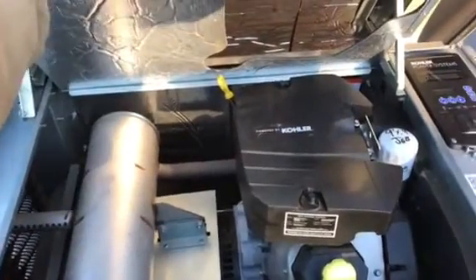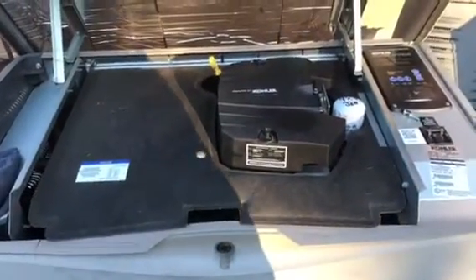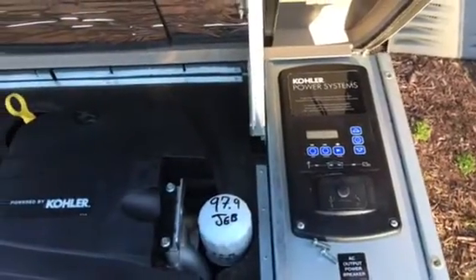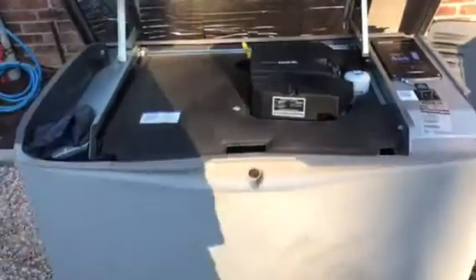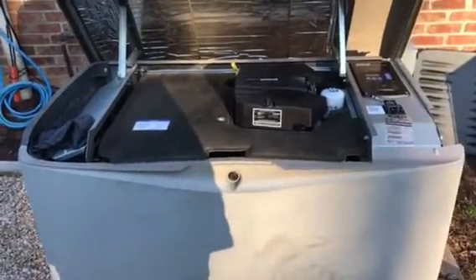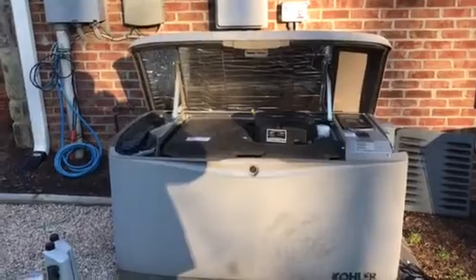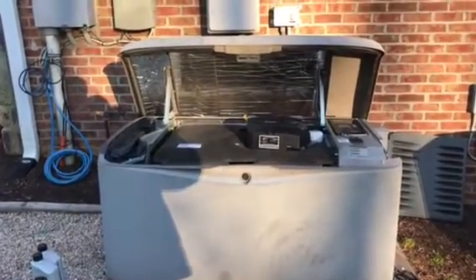We added a little bit of oil because I came out here and it was empty. That is a locked up engine from running out of oil. This generator is now a boat anchor and needs to be replaced. Brand new generator, 90 hours on it. Nobody checked the oil, ran it out of oil, and now they need a new generator.